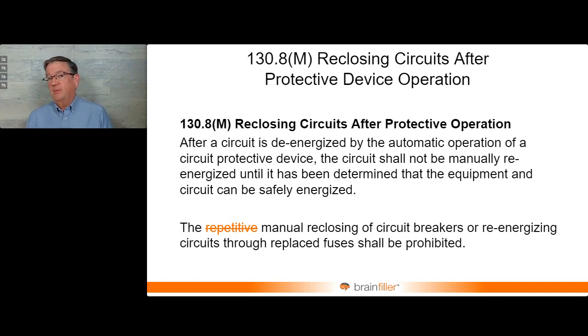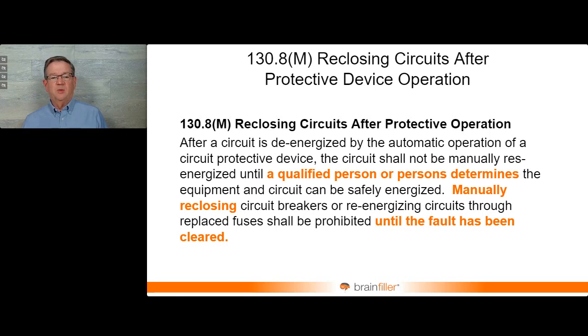Fortunately, we heard all the commotion and knew what had happened. The drill bit went right through the conduit, right through the conductors, tripped everything out. Had we not seen all the commotion, our knee-jerk reaction would have been, let's figure out which breaker it was and reset it. And we would have closed the breaker right back into a pretty nasty fault that they had. So that's what this is all about. You have to determine why it tripped before you reclose it.